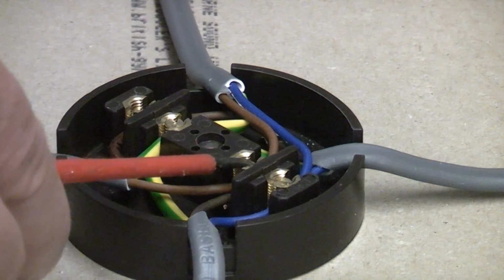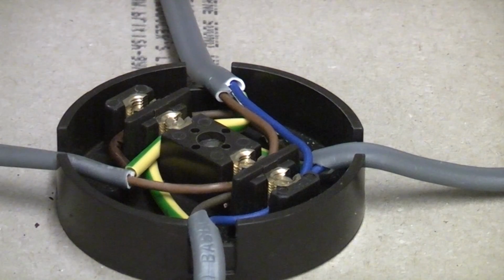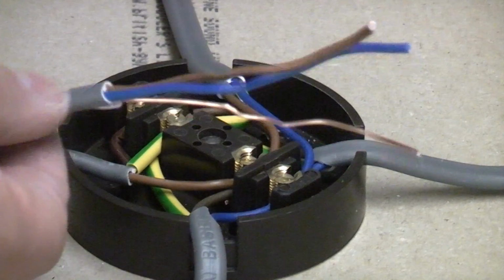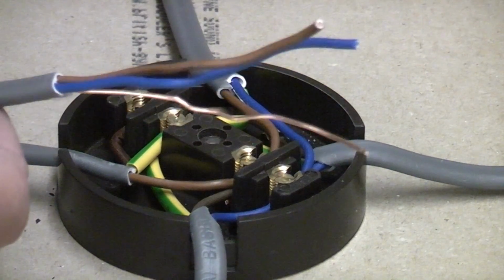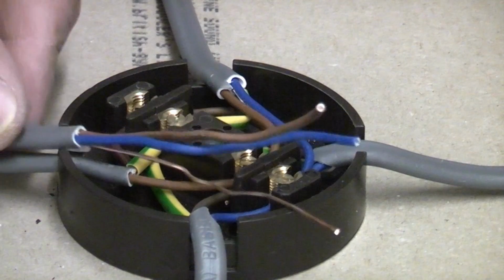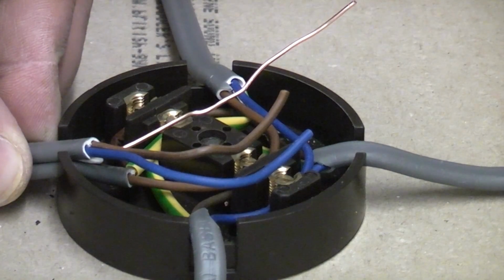We need a neutral in there, a live in there and an earth in there. This is the cable that connects to the FCU that we've just installed, so that needs to go in there. We need to get the earth wire into the earthing terminal, the live wire into the live terminal and the neutral into the neutral terminal. So we just need to trim a couple of those off a bit.